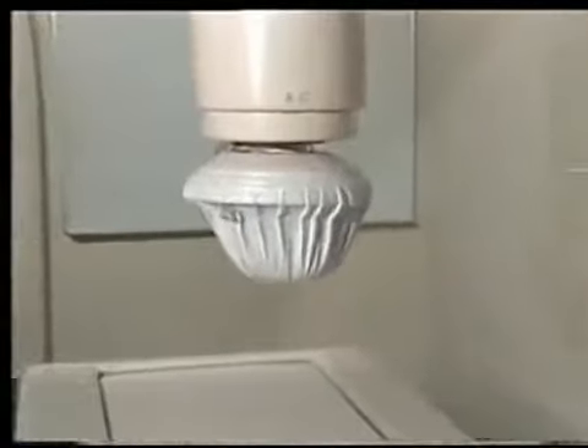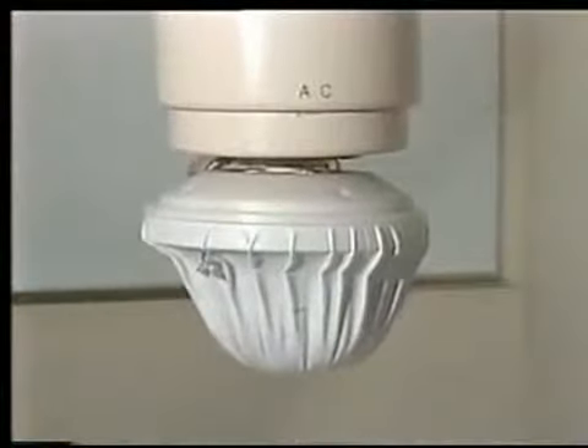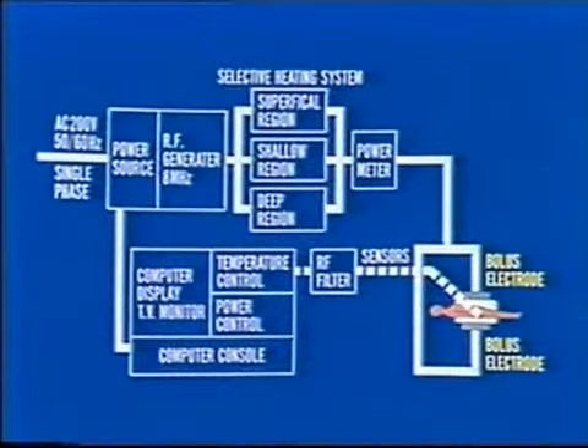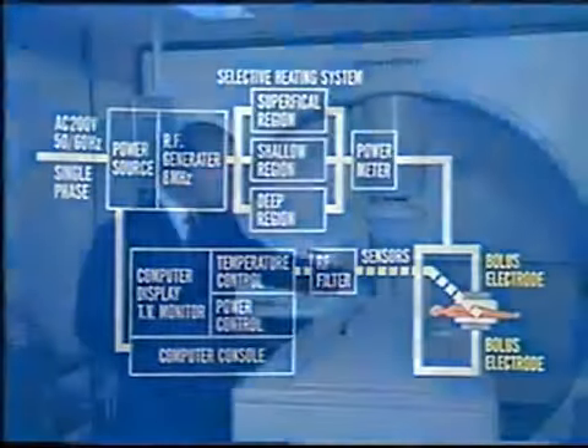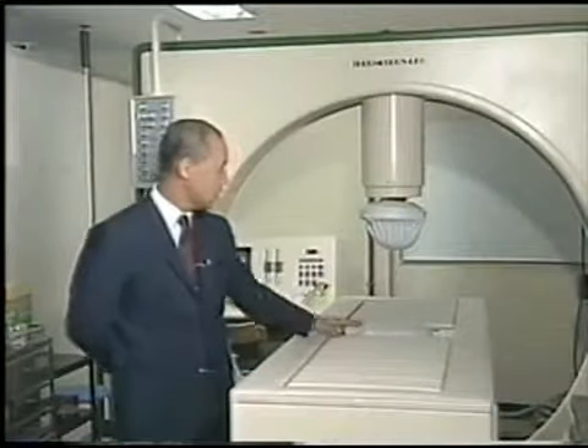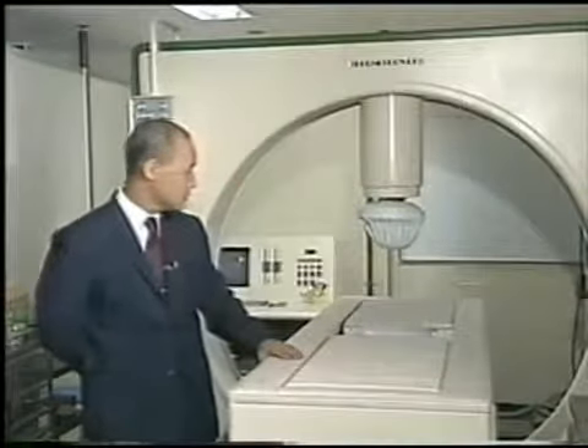The body of the heating system is behind the bed. This is where the energy is emitted. The energy goes into the electrodes and heats the patient's body, which is between them. As I will explain later, the cooling system is very important. Cooling water circulates around the electrodes to cool the surface of the body.